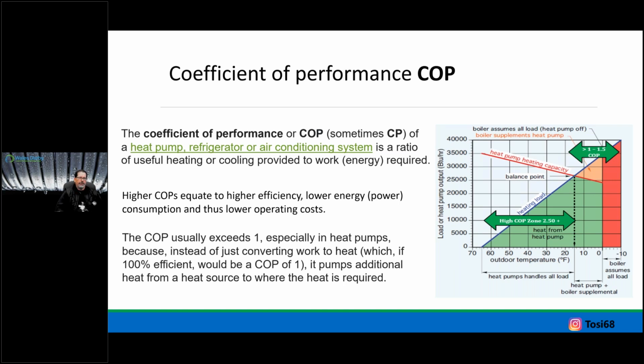The refrigerant is so efficient in how they run. Inverter heat pumps, right? Two-stage heat pumps. There are differences on that side as well. I'm not a refrigerant guy, that's okay, because a lot of the equipment that I'm going to show you in the next few slides is sealed. It has the refrigerant. You don't have to touch it. All you are now is that heating guy on the energy side as well, doing your pumping and piping. Let's open up that installation instruction manual and go, okay, I need a pump to flow a minimum of 8 GPM. That's my job. What pump in our world does 8 GPM and overcomes head resistance, right? Nothing new. We've been doing that forever. Pumping and piping, using a refrigerant electrified heat pump now to get that heat energy out.